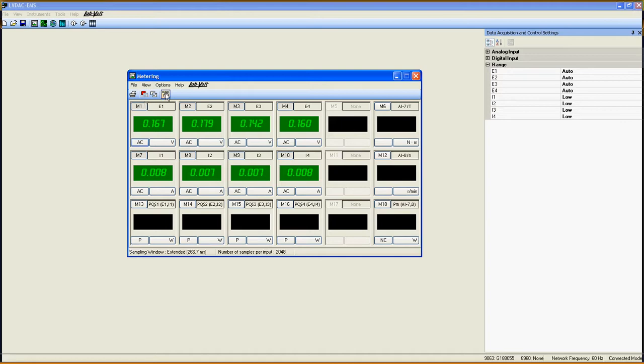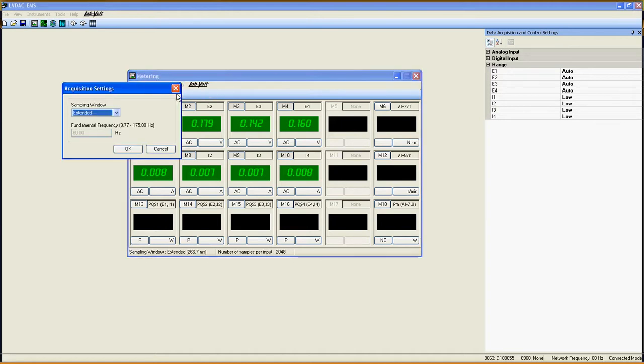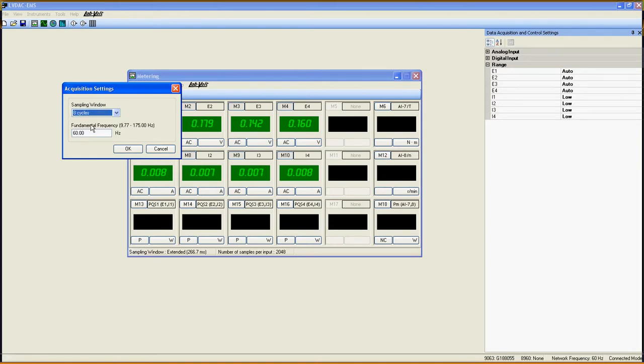Let's return to the acquisition settings here. In this window, you can set the sampling window you want to use and the fundamental frequency. It is suggested to set the same frequency as the network you are working on for more precise results.